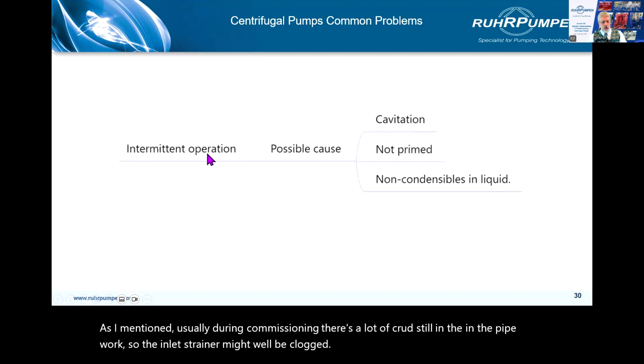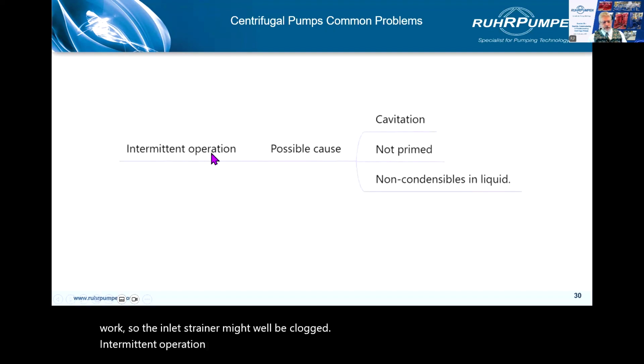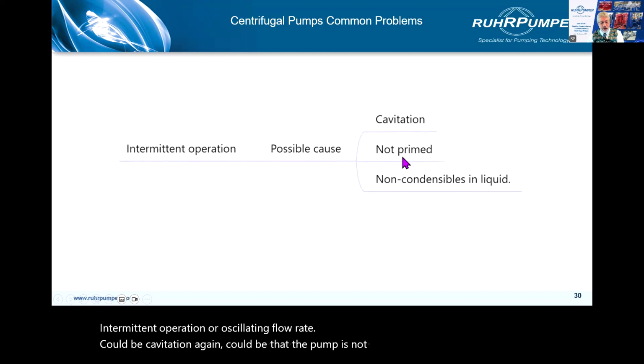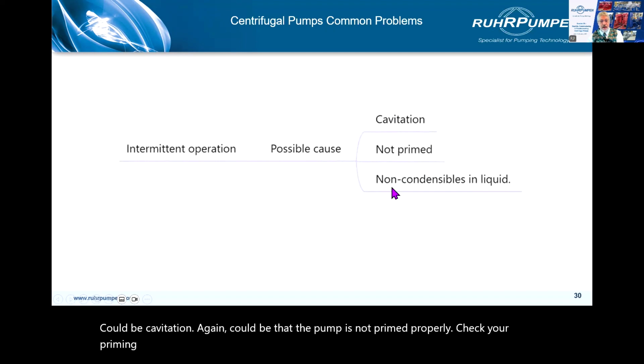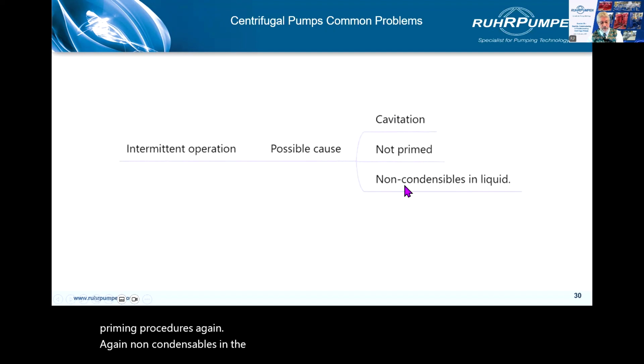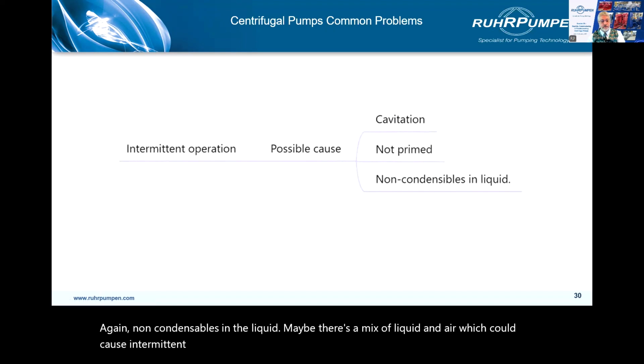Intermittent operation or oscillating flow rate. Could be cavitation again. Could be that the pump is not primed properly. Check your priming procedures. And again, non-condensables in the liquid. Maybe there's a mix of liquid and air, which could cause intermittent or oscillating operation.